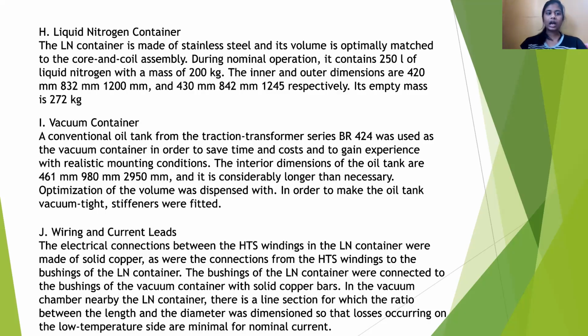Vacuum container. A conventional oil tank from the traction transformer series BR 424 was used as the vacuum container in order to save time and cost and to gain experience with realistic mounting conditions. The interior dimensions of the oil tank are 461 mm, 980 mm, 2950 mm. It is considerably longer than necessary. Optimization of the volume was dispensed with. In order to make the oil tank vacuum tight, stiffeners were fitted.